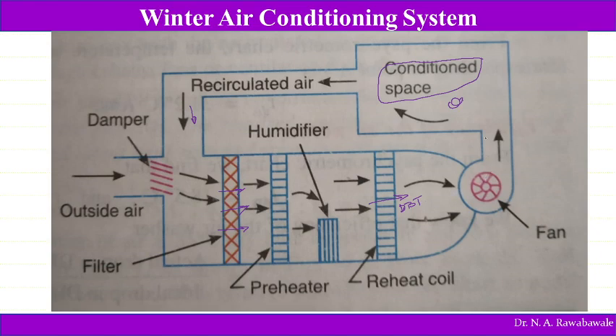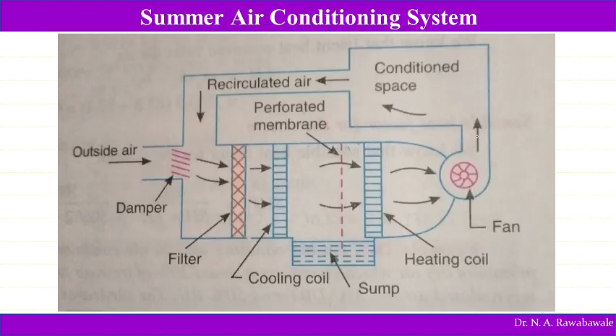In winter, the outside dry bulb temperature is lower, so we need to increase the dry bulb temperature of the room as well as the humidity. Winter humidity of air is low, so the humidifier and heater play very important roles to increase both temperature and humidity. The filter helps maintain purity of air, while the blower helps maintain the velocity of air into the conditioned space. This is what is known as the winter air conditioning system.